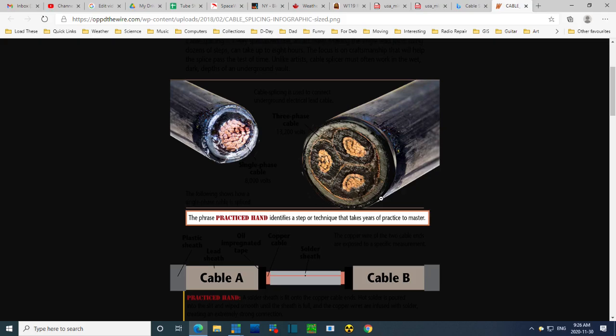And the oil they put in these, I can talk all day on this. The oil they put in these in the early days was, I don't know if it was vegetable oil, but it wasn't stable. And the oil would slowly turn into wax. It would hydrogenate inside the cable. The problem with that is wax doesn't flow. The oil can move around a little bit. Even though there really isn't a lot of excess oil in these things, there is a bit, and it'll flow into gaps, holes. Again, maybe in this area where construction is difficult, the oil will fill up any gaps that are in here.